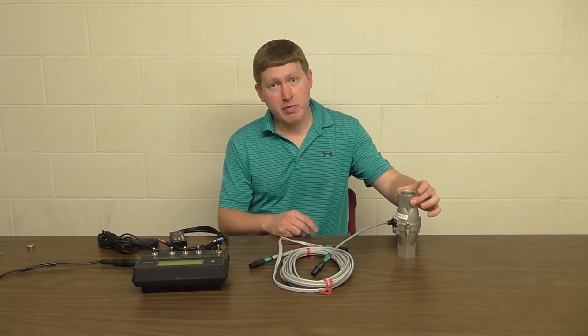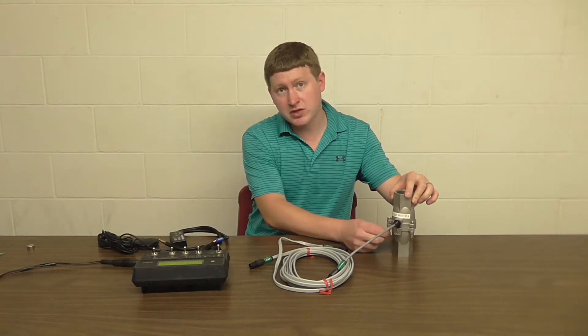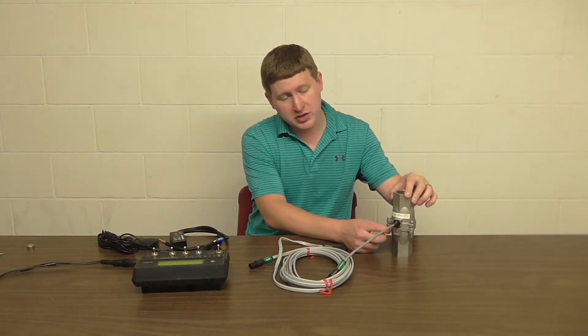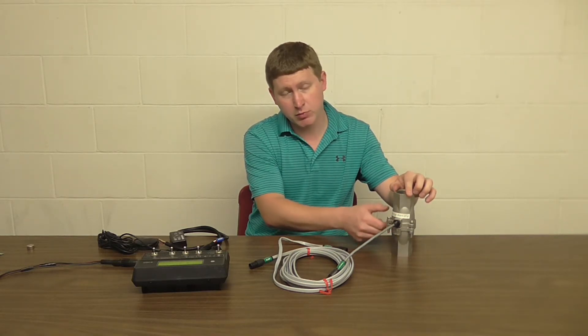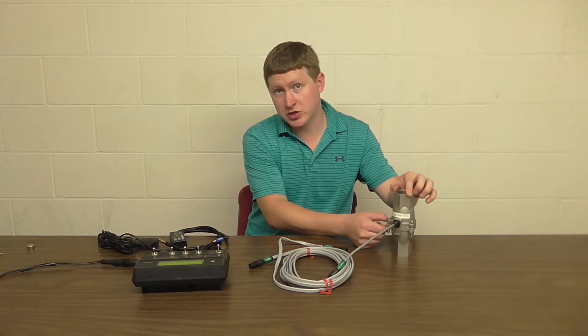When you put the unit back together, these three bolts are going to be torqued to 100 inch pounds. Going tighter than that can damage the bushings and the bearings, or crush the O-ring.